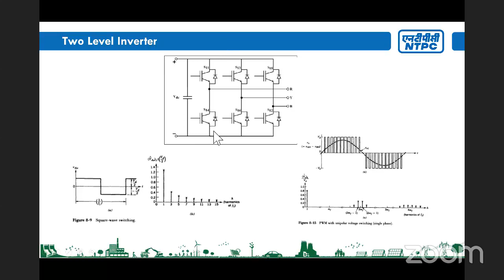Initially the topology was two-level, because the module maximum DC voltage rating is around 1000 volt, and IGBT devices generally come with a 600 volt rating. So two devices are sufficient for a two-level topology. On the module side we have a limitation of 1000 volt, and on the inverter side, because of the IGBT rating, the two-level configuration was very suitable at that time.